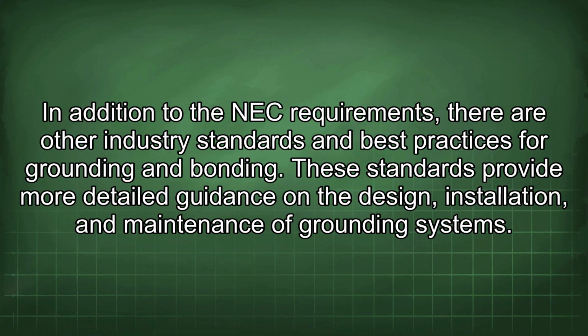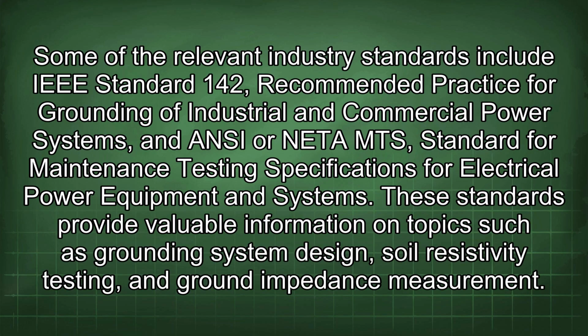In addition to the NEC requirements, there are other industry standards and best practices for grounding and bonding. These standards provide more detailed guidance on the design, installation, and maintenance of grounding systems. Some of the relevant industry standards include IEEE Standard 142, Recommended Practice for Grounding of Industrial and Commercial Power Systems, and ANSI/NETA MTS, Standard for Maintenance Testing Specifications for Electrical Power Equipment and Systems. These standards provide valuable information on topics such as grounding system design, soil resistivity testing, and ground impedance measurement.